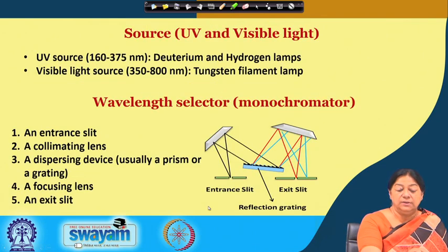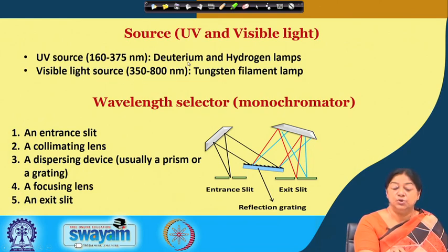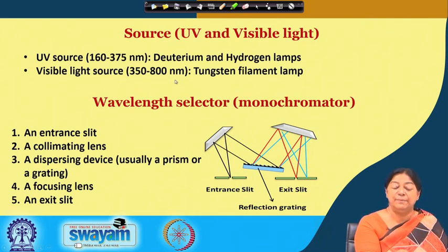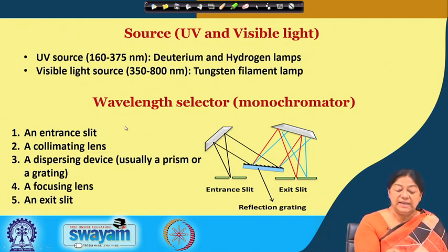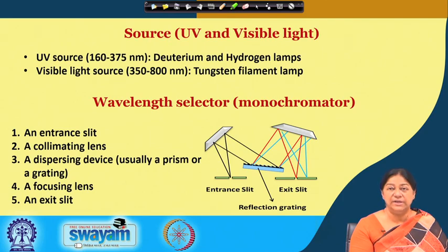When we look at UV and visible light sources, the machine has a UV source and a visible light source that cover two different wavelength regions. We have the deuterium lamp (D2 lamp) covering approximately 160 to 375 nanometers, and then the tungsten filament lamp for the visible light source, slightly overlapping in range. The wavelength selector is essentially a reflection grating that selects the specific wavelength of interest for our measurements.